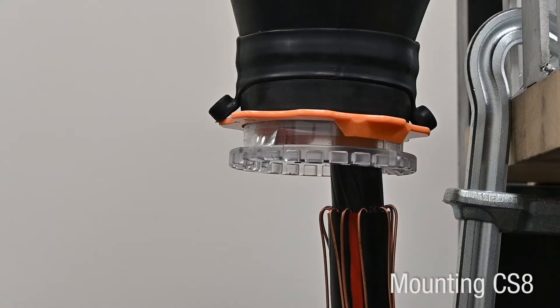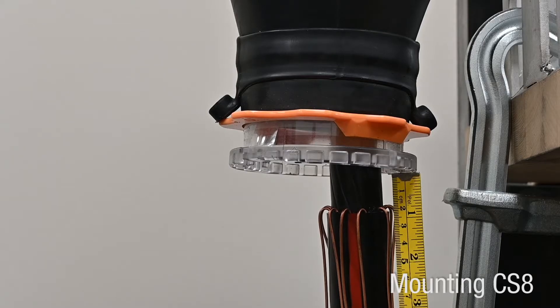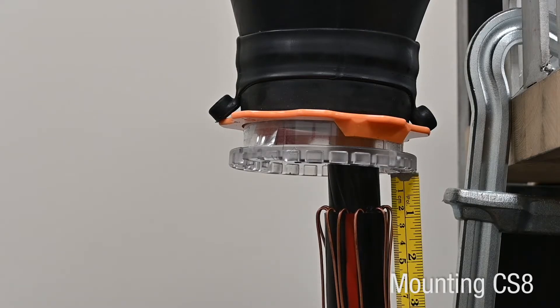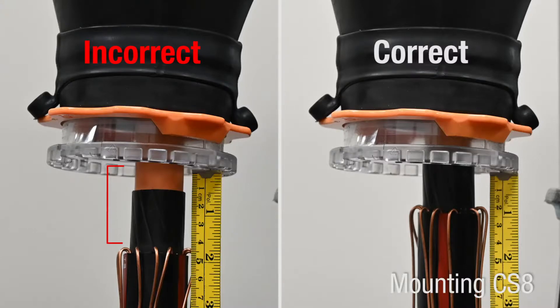Re-measure distance from the edge of the core to the jacket cutback. Confirm this distance has not changed more than 3 quarters of an inch. If the cable has shifted, assembly must be redone. Contact the factory for more details.